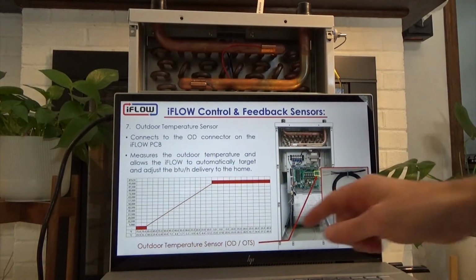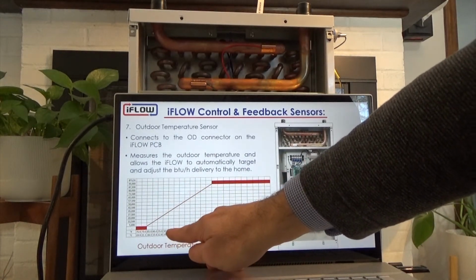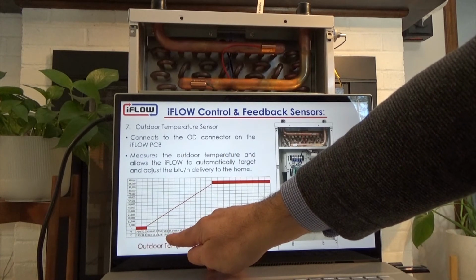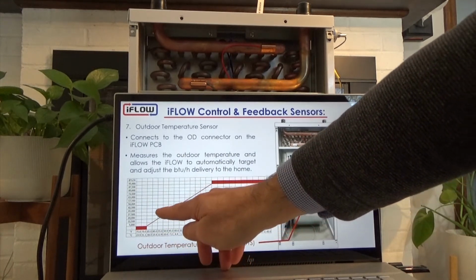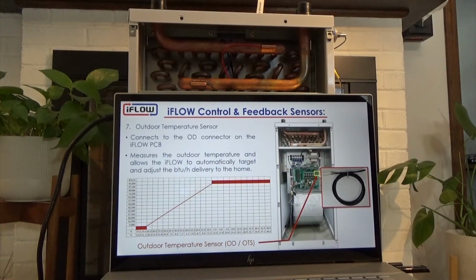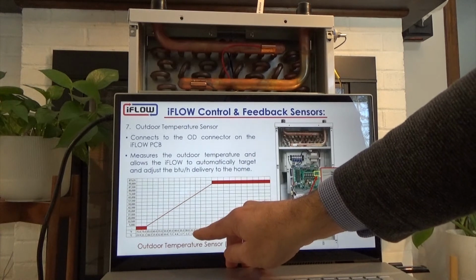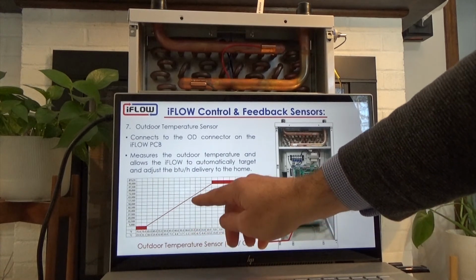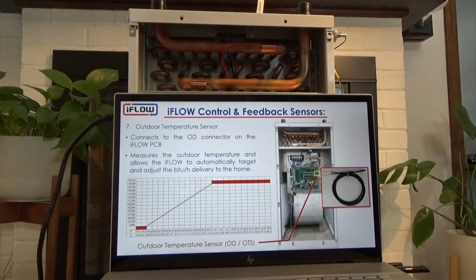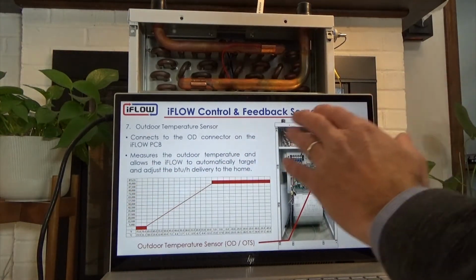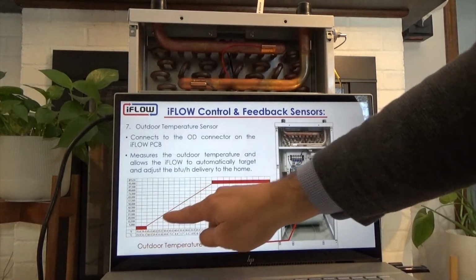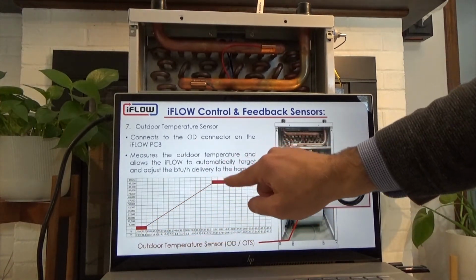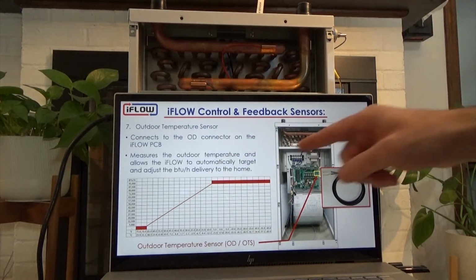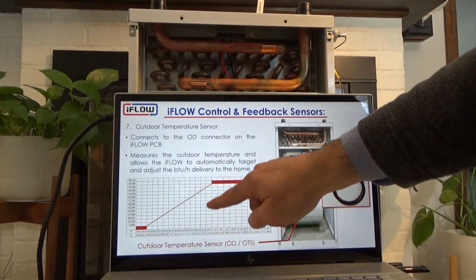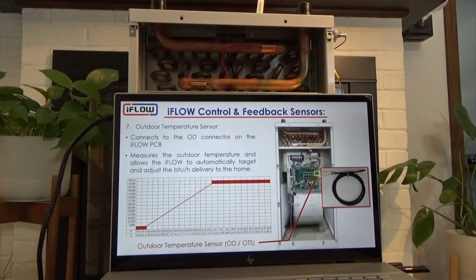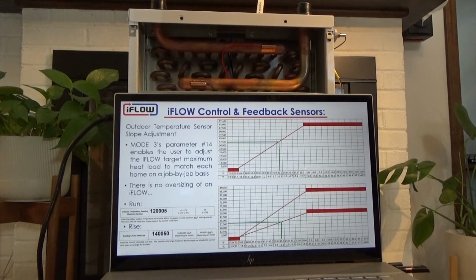So for example, if the outdoor temperature is 45 degrees or 7 degrees Celsius, then we're going to be delivering, go up to the curve, about 35,000 BTUs. If the temperature outside is 20 degrees Fahrenheit or -7 degrees Celsius, then we go up to the curve, go across, about 70,000 BTUs. So all to say that we will vary the amount of BTUs delivered based on these two set points. Now, based on this set point, you have both the BTU input and the outdoor temperature where you need that maximum demand.